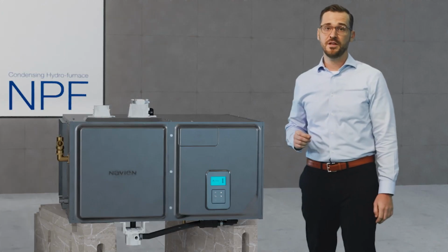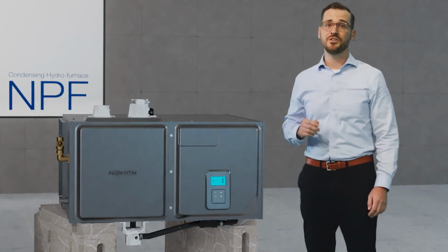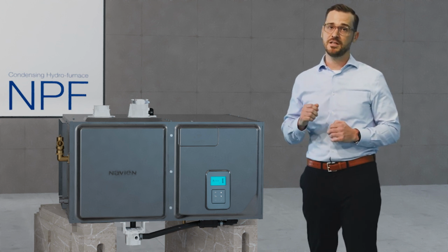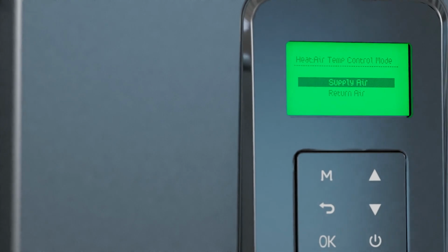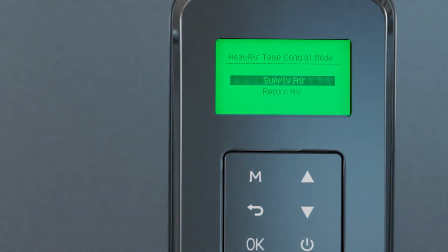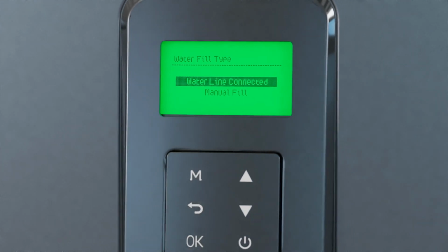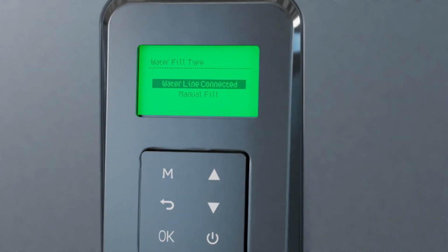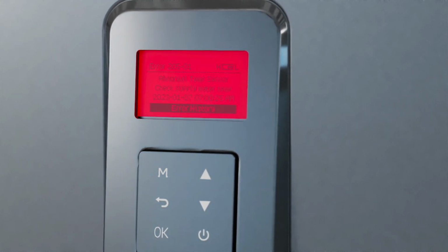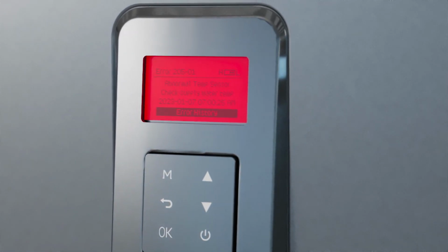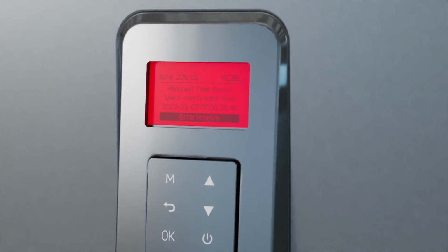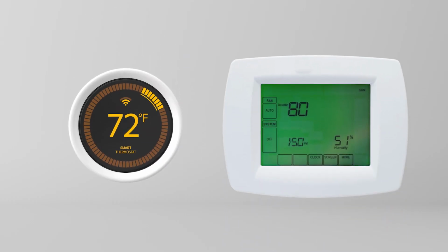The familiar EasyNav interface with built-in setup wizard provides easy, intuitive steps for startup, configuration, and diagnostics. Installers can set supply temperature and airflow directly from the front panel, and the service wizard will walk you through component verification to aid in troubleshooting. The self-diagnostics provide a direct readout and clear text indicating any diagnostic alerts or reminders saved in non-volatile memory. Each unit is compatible with most 1- and 2-stage thermostats and does not require a special wall control. Customers can keep the thermostats they're already familiar with while reaping the full benefits of variable capacity.